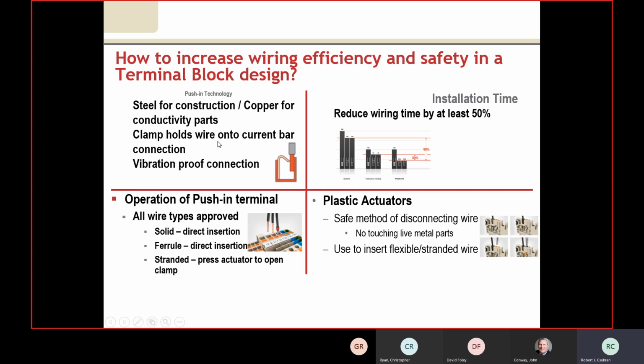This just shows how the clamp is held down. In the case of the spring clamps, you've got to insert a plastic device or a small screwdriver to slide it in. In the case of the push-in terminal blocks, we have two ways of handling that. One of them is with a ferrule that you mount on the end. The other one is with solid wire. If you are going to use stranded wire, you can do that with the push-in terminal block, but you do then need to use the plastic insert device or a screwdriver to allow those to get inserted. Now, notice the reduction in wiring time by at least 50%.